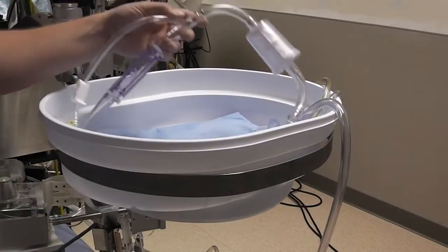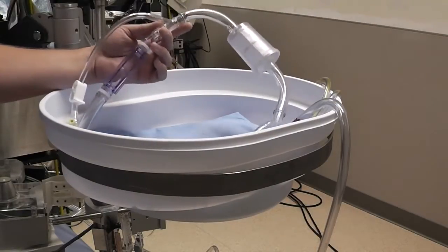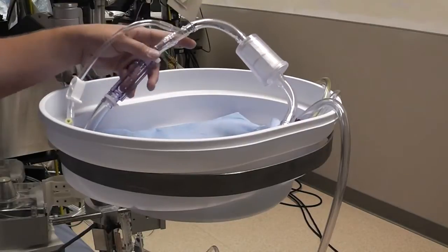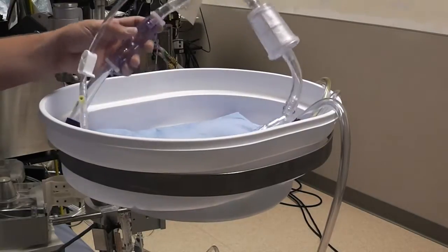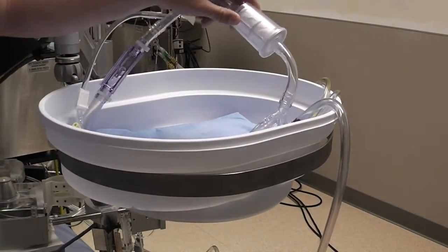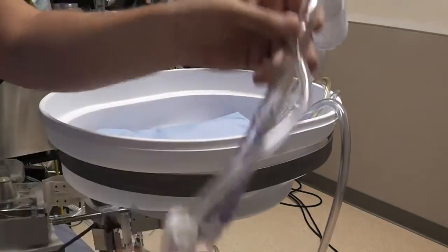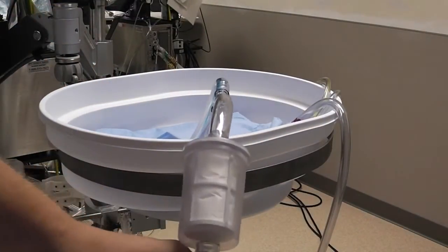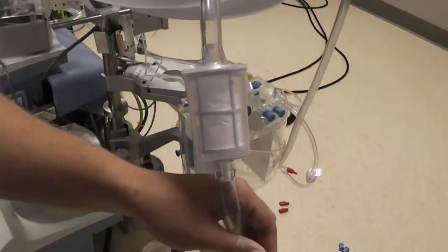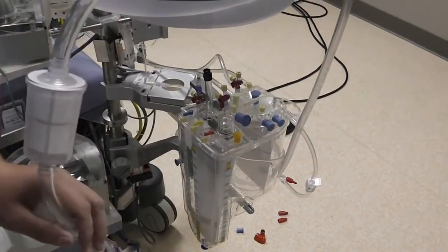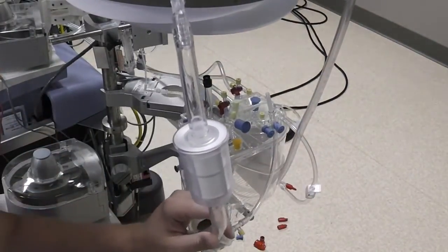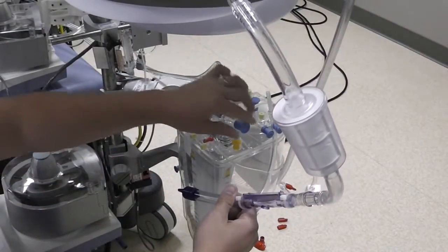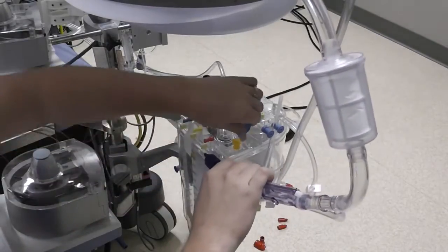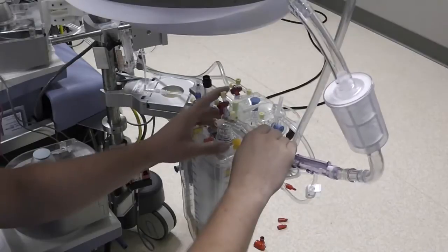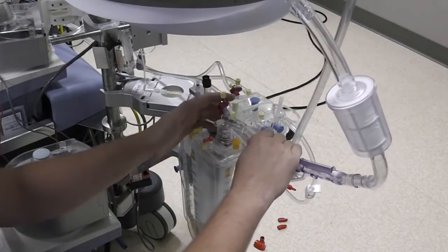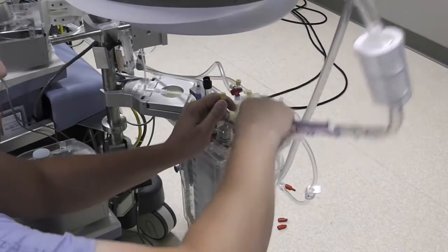Next we're going to attach the venous line to the reservoir. So that should be pretty much the last thing in your basket here if you pulled all the other ancillary stuff out. So you'll see this, we have our pre-bypass filter on here, and we're just going to roll this out of the basket. Come down here. We're going to take this line and just tuck it over here for now. And this is where we make our venous connection. So we're just going to remove these caps and make this connection, being careful to support this in the back as we push it on so that we don't break anything.